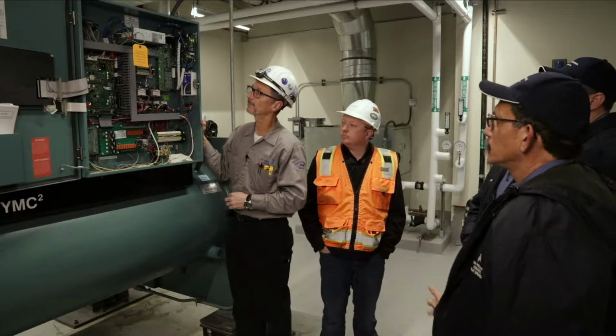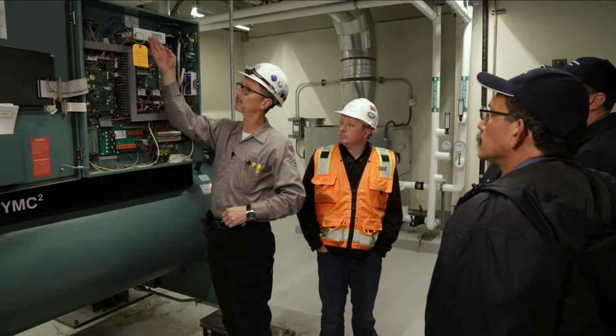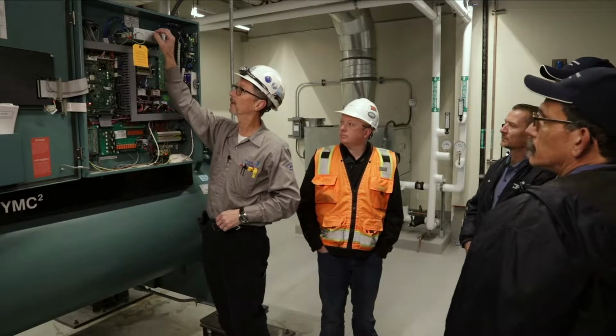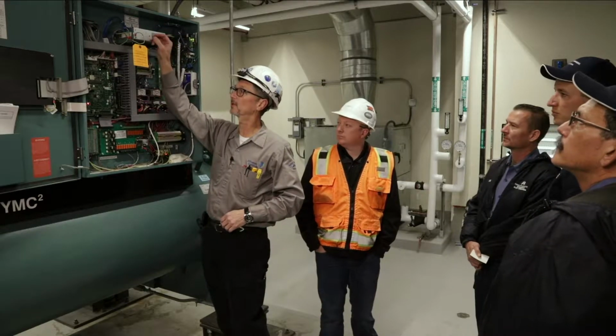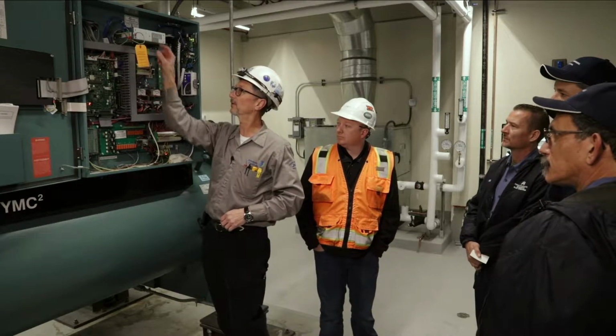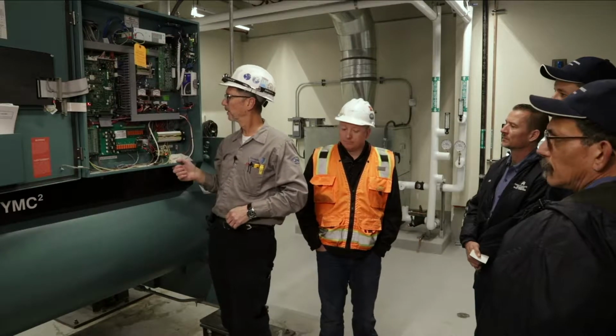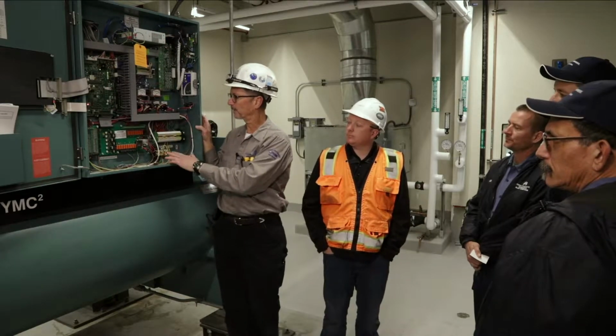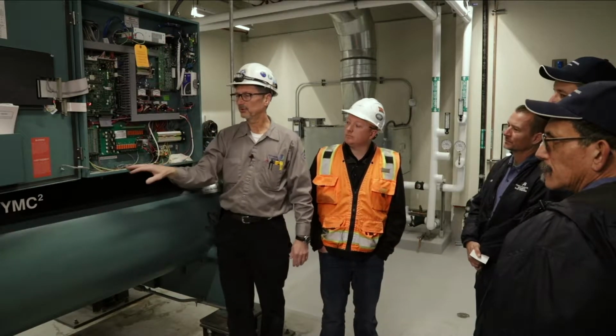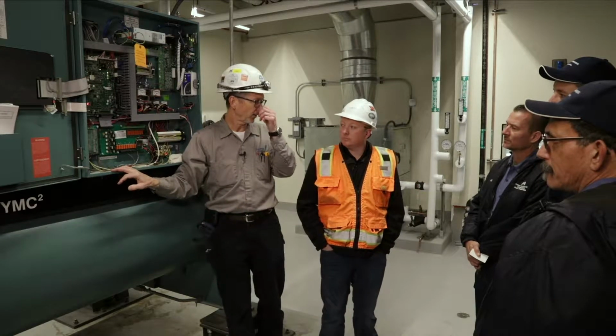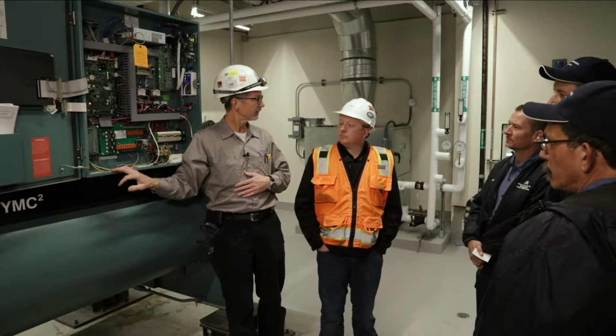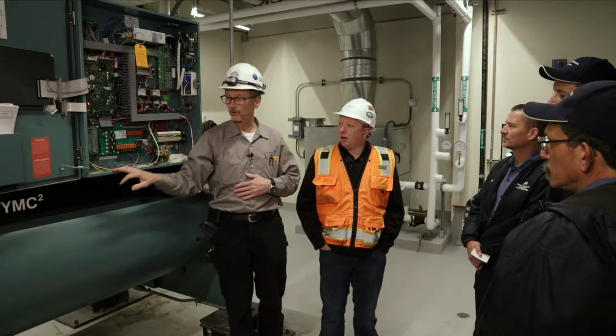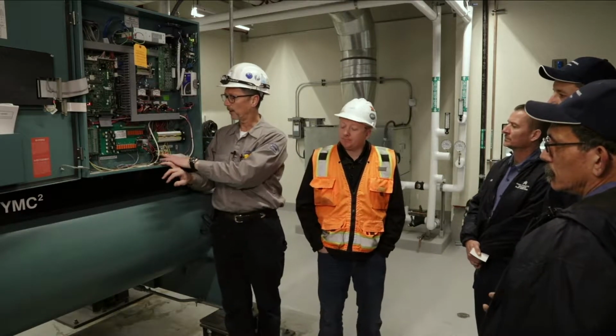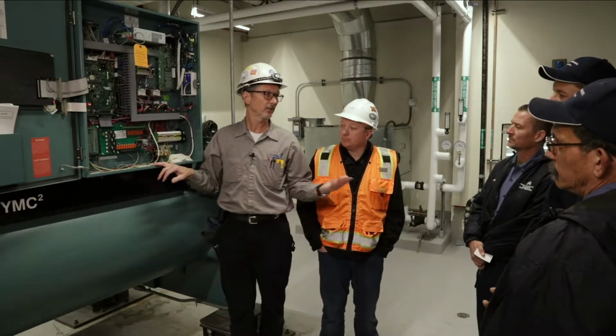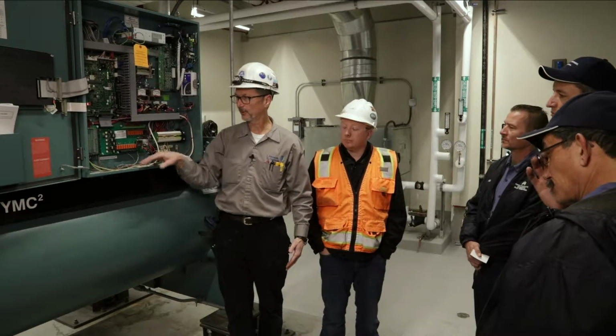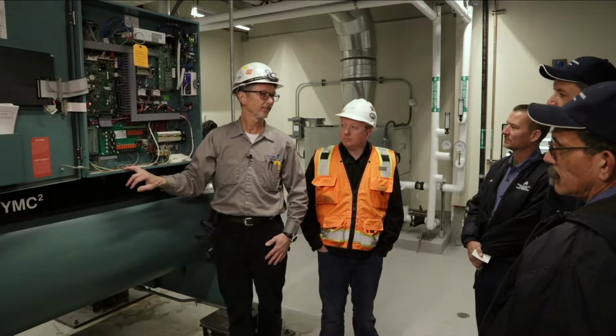This is the link to it. Power supply gives 115 volts comes in and distributes power throughout different components in here through the power supply. And then there are some control relays down here for a digital control. Is this going to be running on ISN or? No, not on ISN. Okay, so hardwired everywhere. So the hardwire will go through the relays. Basically, energy management will control the relays, which in turn starts and stops the chiller.